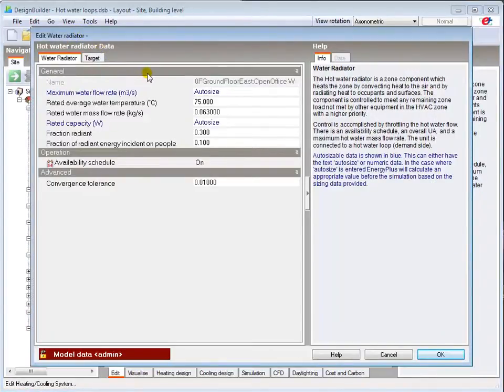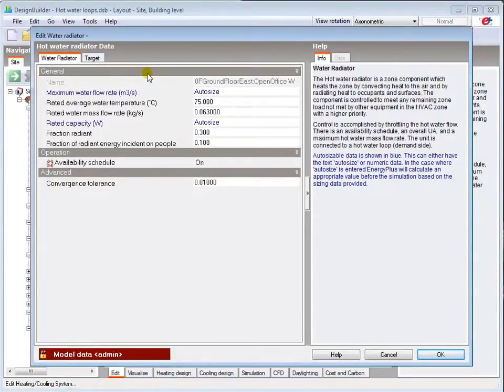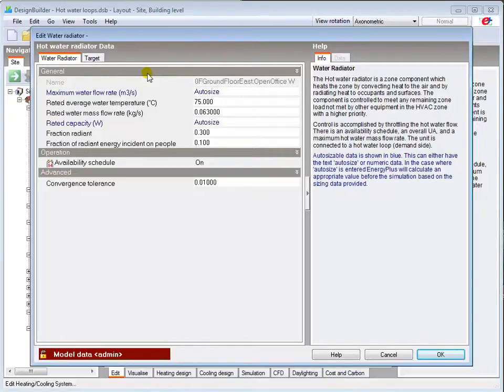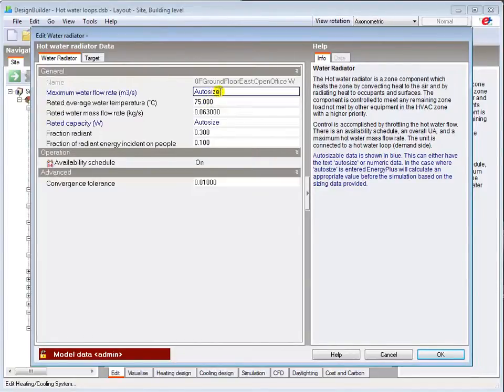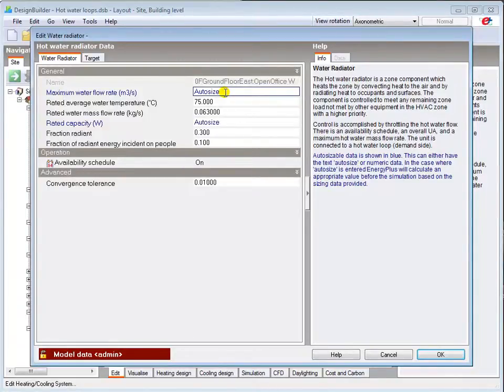The radiator is modelled as a constant temperature variable flow component. So as the zone temperature reaches its set point, the radiator valve will reduce the flow of hot water from the loop to the radiator. The maximum water flow and rated capacity can be auto-sized, or you can input both values manually from design data.